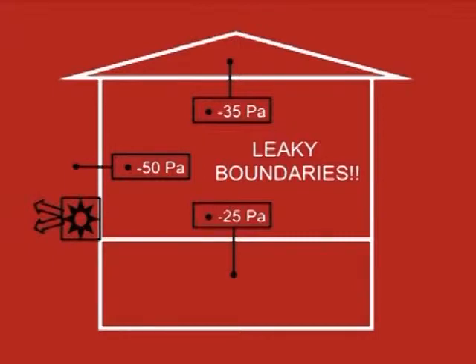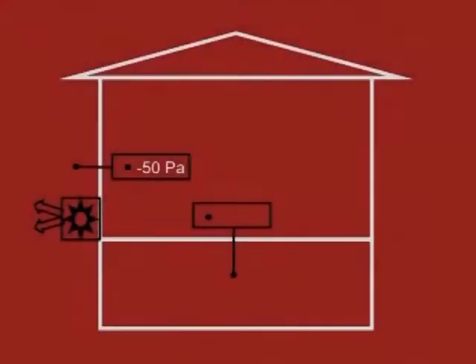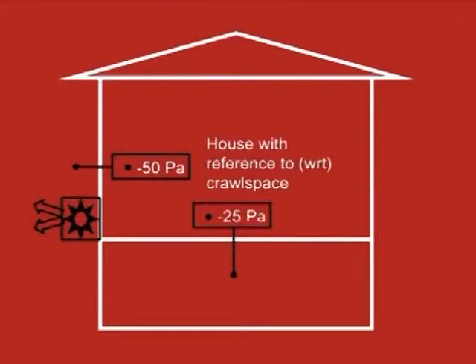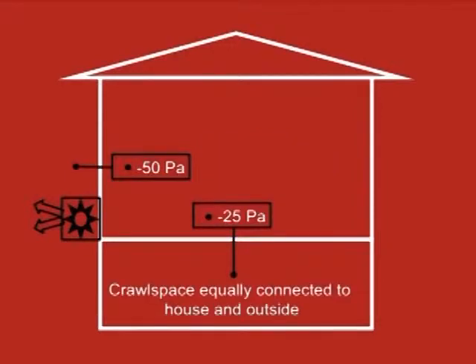The extent of the leakage depends on the recorded value. For example, if we are running the blower door and we want to see how connected the crawl space is to the interior and to the exterior of the building — if we measure the house with reference to the crawl space and we record a pressure difference of minus 25 pascals, we can say that the crawl space is equally connected to the interior and exterior of the building.